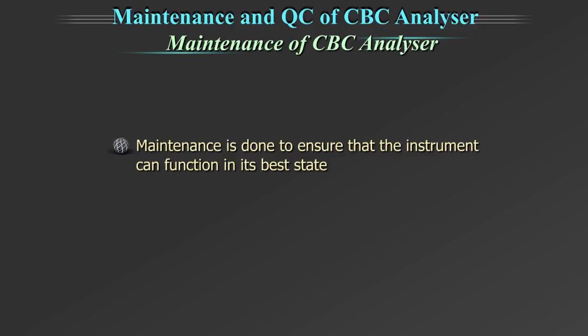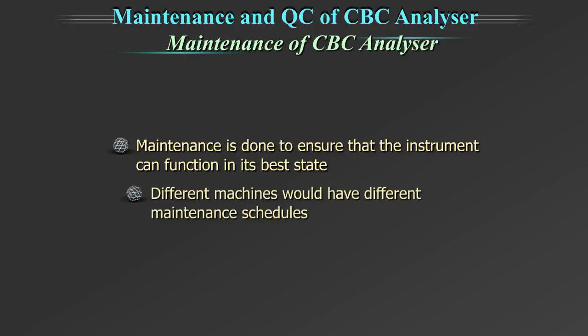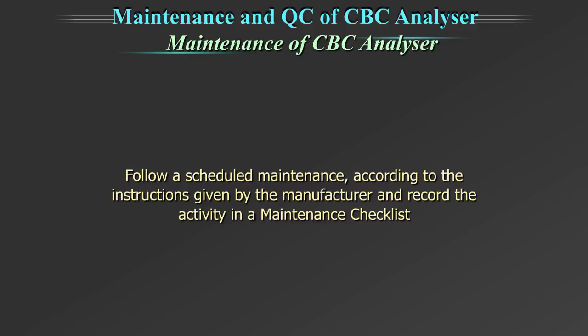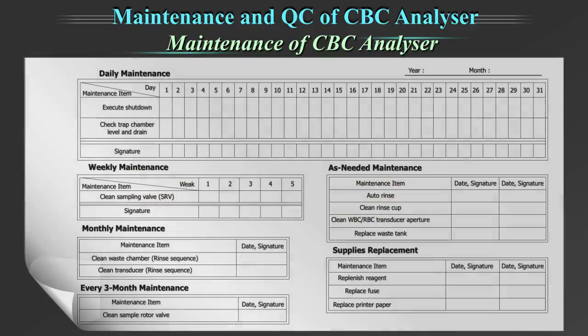Maintenance is done to ensure that the instrument can function in its best state. Different machines would have different maintenance schedules. Follow a scheduled maintenance according to the instructions given by the manufacturer and record the activity in a maintenance checklist. In addition to the daily maintenance, weekly, monthly, and as needed maintenance should be performed by the lab as per the manufacturer's guidelines. For example, you can see a maintenance chart of KX21 on the screen.